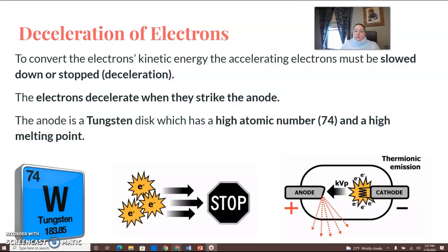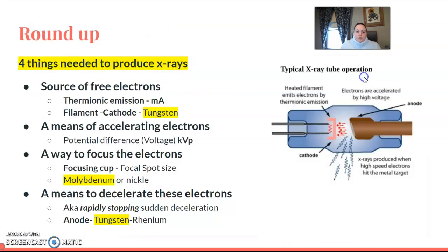We need a deceleration or a way to stop or slow down the electrons. The KVP kicks the electrons into gear from the cathode and shoots them over to the anode. They connect with the anode, which is made of tungsten, and that's where they decelerate. The anode is a tungsten disk with a high atomic number (74) and a high melting point.